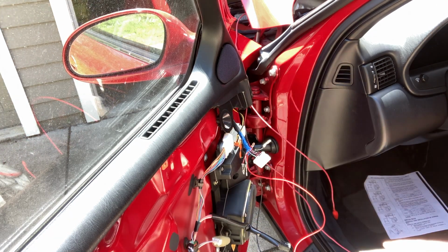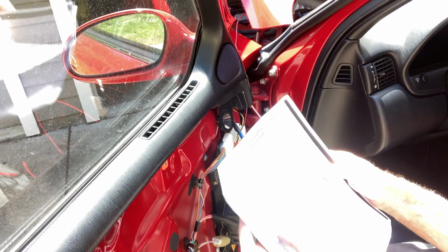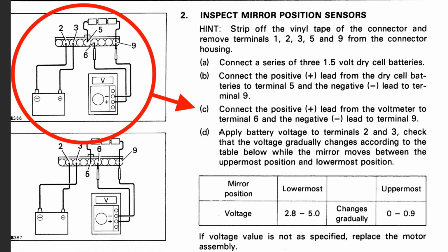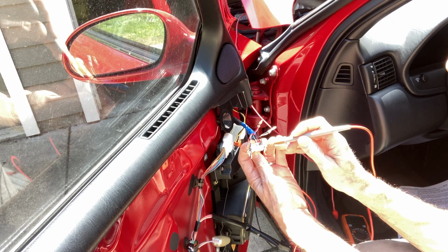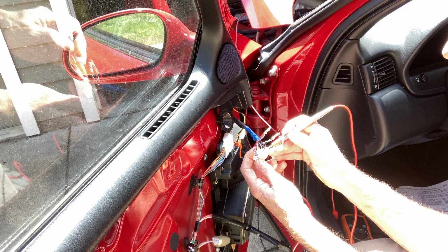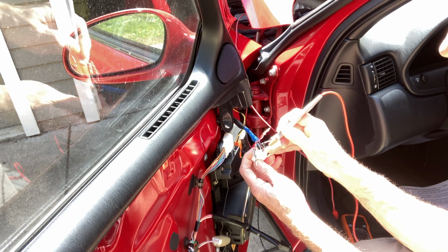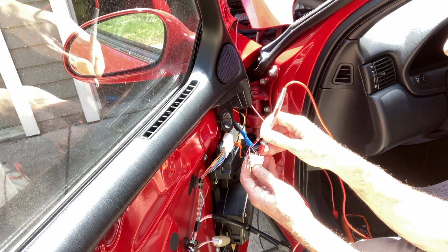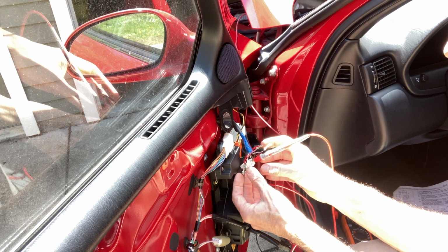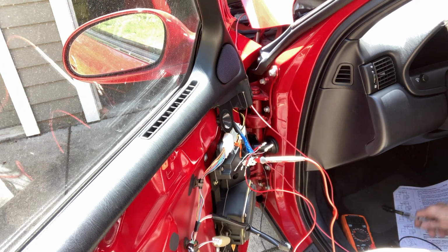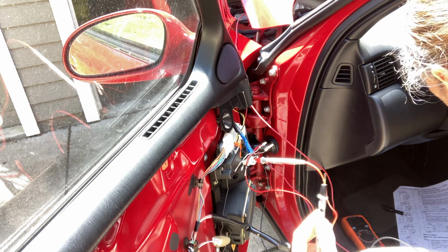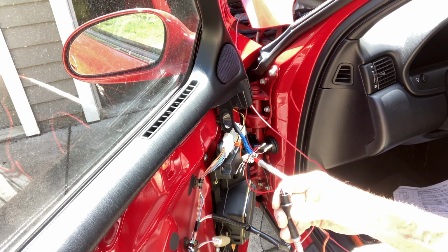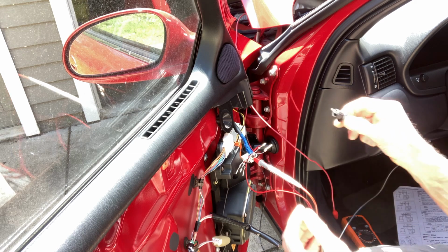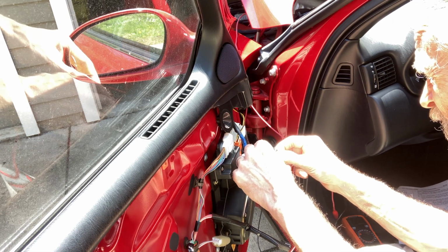All right. Those are juiced up. Then connect the positive lead from the voltmeter to terminal 6 and negative to 9. Terminal 6 is still in my connector, and that's fine because I'm going to jam my probe down in here to touch that terminal, so I don't actually have to take it out. But then the negative lead has to go to 9. I'm going to put this alligator clip on here and grab 9.